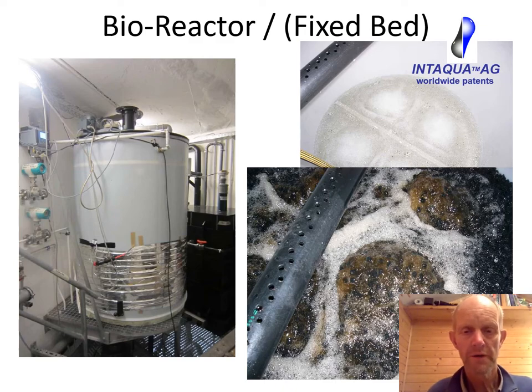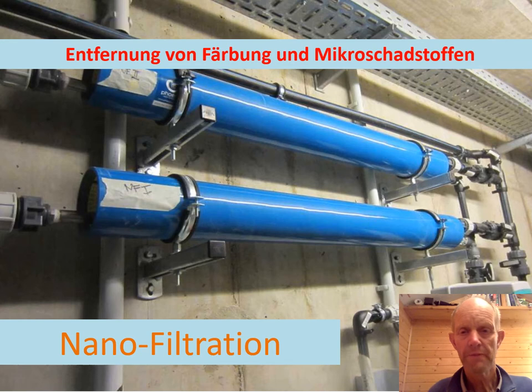We can do further research there as well. This is the nano filtration unit, which is needed to remove the dyes from the black water — otherwise it would have a yellowish appearance in the toilet bowl. The black water loop system can also remove all pharmaceutical residues, produce highly concentrated dry crystalline nutrient powders, while solids are separated and can be processed like terra preta to compost for replenishing the humus.